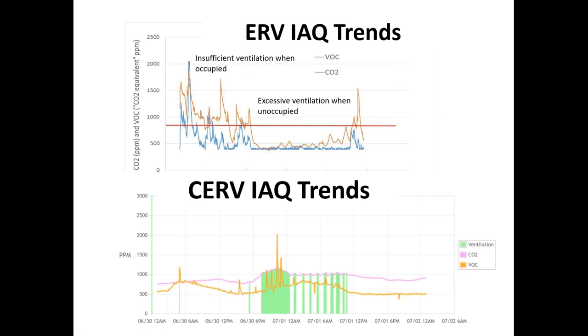These are just some graphical representations of conventional ERV operation versus CERV smart ventilation operation. The top figures show CO2 and VOC levels in a high performance home just with ventilation set to the ASHRAE standard. So you can see it's insufficient when the building is occupied, kind of the first part of that graph, the orange and the blue. And then when the occupants have left the space, that's the ideal air quality, but it's overventilating. It's at minimal level outside, but the system continues to run in ventilation mode, even though it's not needed. And then when occupants return to the space, then it's no longer adequate.